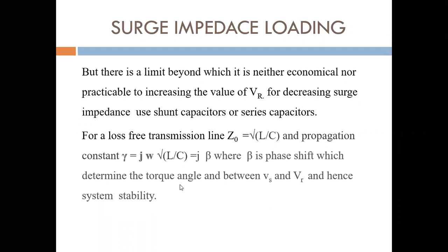The propagation constant gamma is equal to j omega root of L by C, which is equal to j beta, where beta is the phase shift which determines the torque angle between Vs and Vr. Thus, with the use of shunt capacitors the surge impedance is reduced, but the phase shift is increased due to the increase in the value of C.